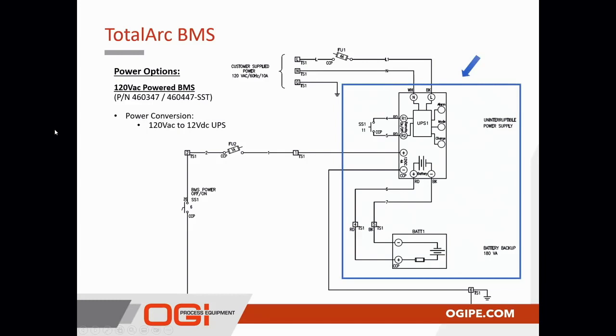Okay, in this case, the 120 volt version provides an onboard UPS system that actually has its own battery, a separate battery supply, up to 10 hours of uninterrupted power if the primary power is lost. Note that this power option is intended for short intermittent power interruptions and not for long-term power loss. If additional duration is required, the customer may want to consider adding or utilizing a UPS supported 120 volt supply to the BMS as an added protection to ensure that the BMS is never going to lose power.